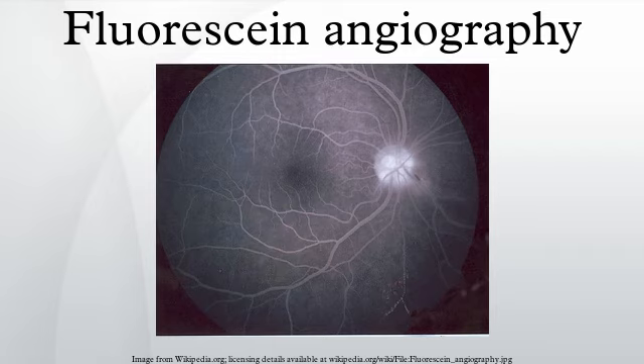Most filters only allow light through at a wavelength of 490 nanometers. The barrier filter allows only yellow-green light to reach the camera. Both filters are interference bandpass filters, which means they block out all light except that at a specific wavelength. The barrier filter only allows light with a wavelength of 525 nanometers, but depending on the filter it can be anywhere from 520 to 530 nanometers.